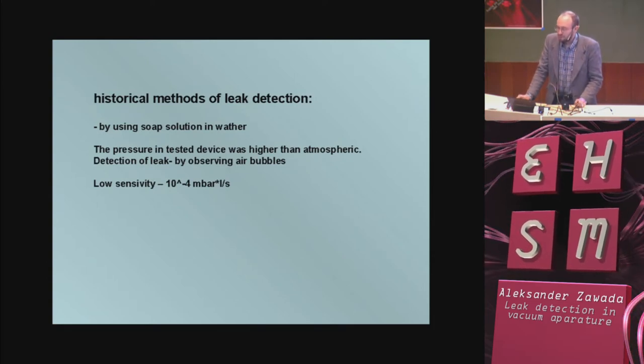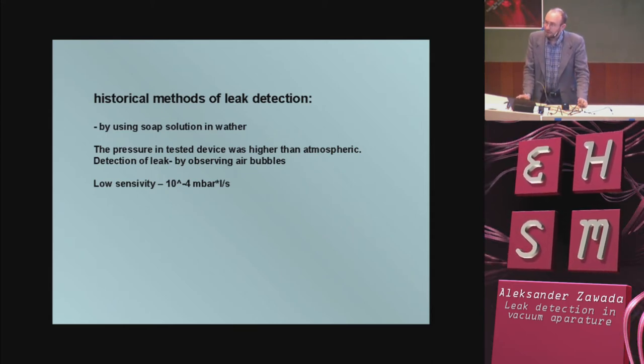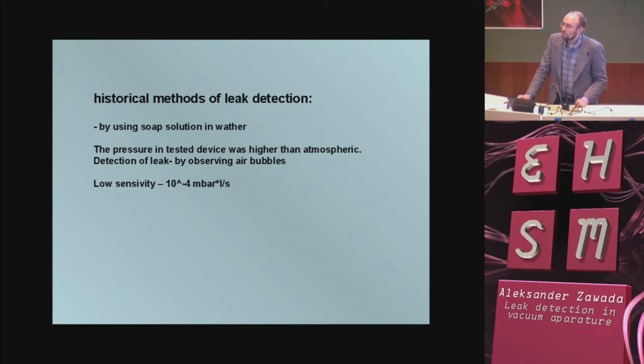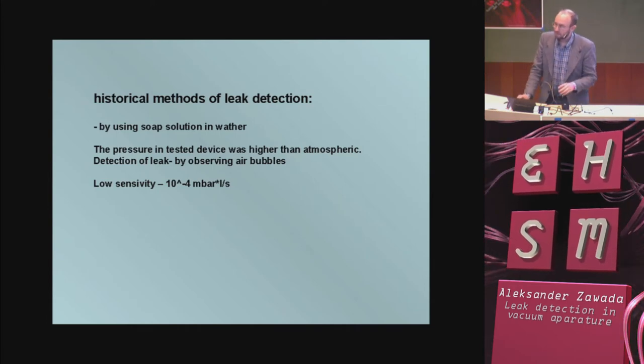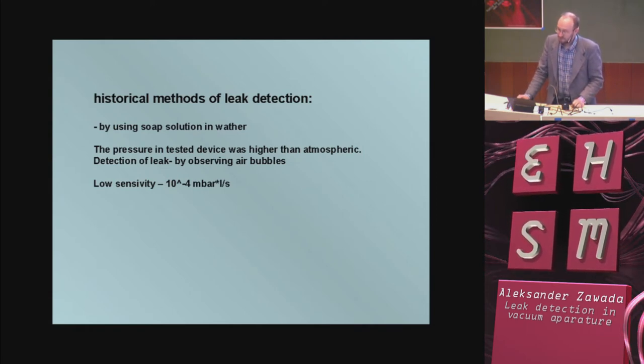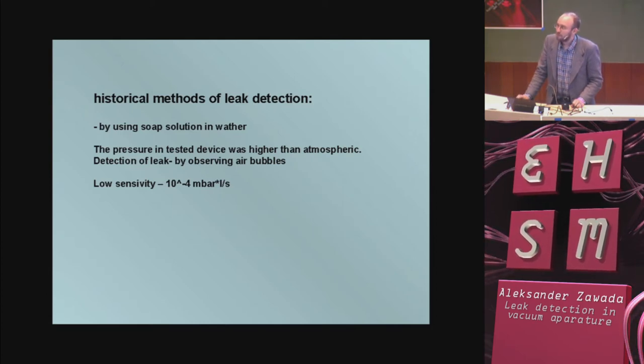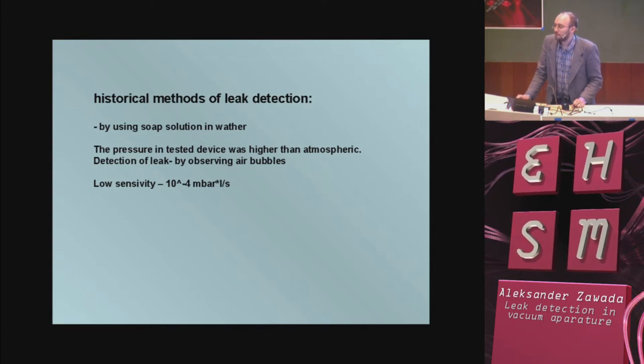About historical methods of leak detection: a very old method was using soap solution in water — you paint part of the vacuum system. Inside the vacuum system the pressure should be higher than atmospheric, and you can observe small bubbles of air from the leak place. This method has very low sensitivity: only 10⁻⁴ millibar·liter per second. It's sometimes used for pressure apparatus, but for vacuum apparatus this method is rather lost.